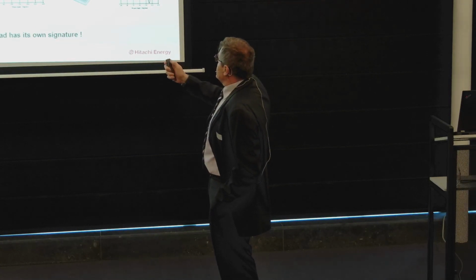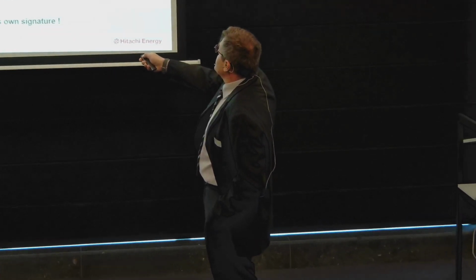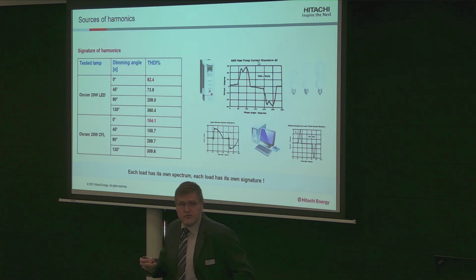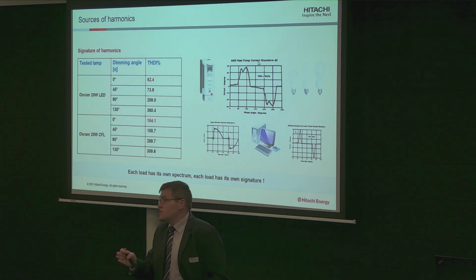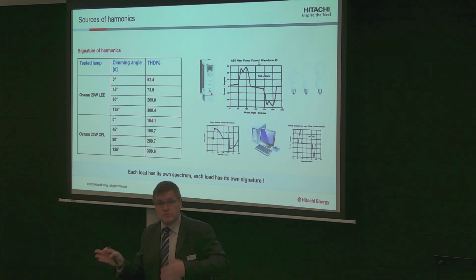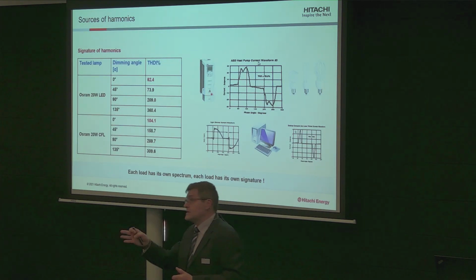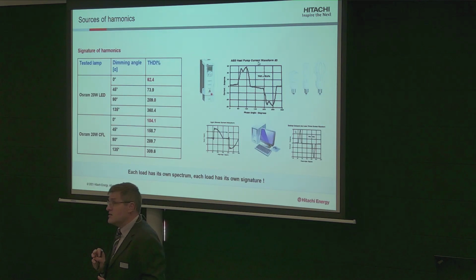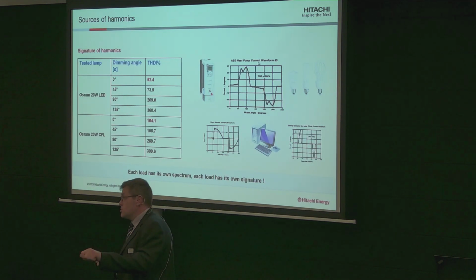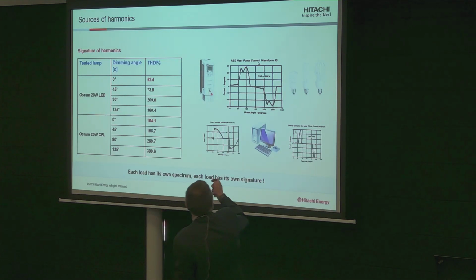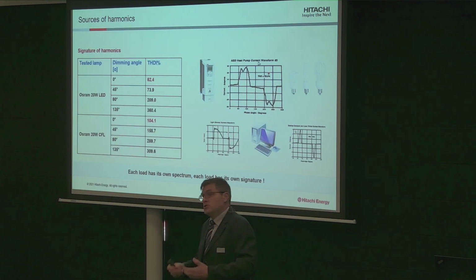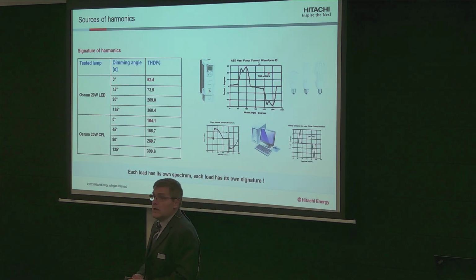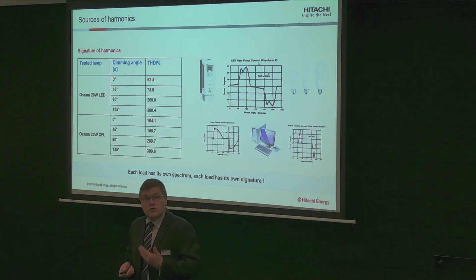Alors, in industry, you have what we call variable speed drives, which nowadays are very good. We change the direct online motors to variable speed drives, so we get 20, 30, 50% energy savings because you just switch your motor on and off when you need it in your process. But the current that you draw, you see it's 53% THDI, generates massive pollution, and so you need to do something.